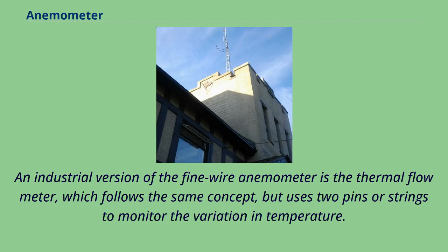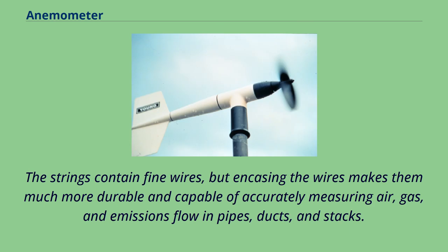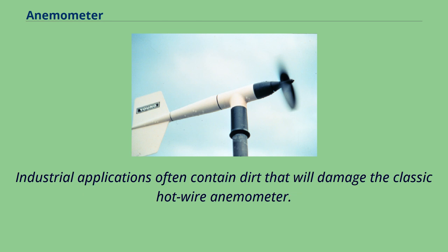An industrial version of the fine wire anemometer is the thermal flow meter, which follows the same concept, but uses two pins or strings to monitor the variation in temperature. The strings contain fine wires, but encasing the wires makes them much more durable and capable of accurately measuring air, gas, and emissions flow in pipes, ducts, and stacks. Industrial applications often contain dirt that will damage the classic hot-wire anemometer.